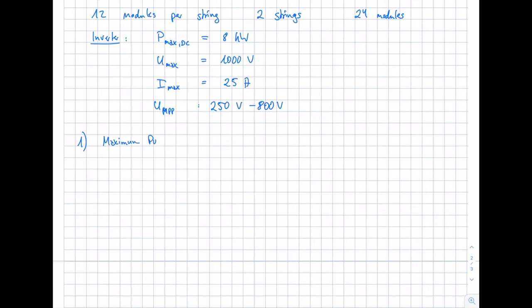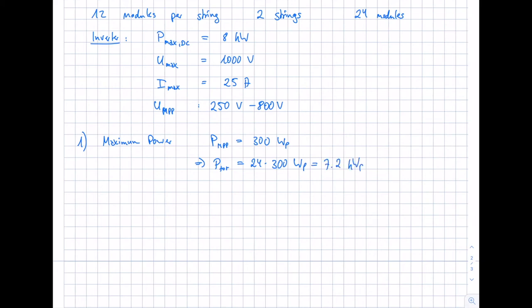Criterion one — maximum power: our module has an MPP power of 300 watts, and we have 24 modules total (12 per string, two strings). That gives us a total power of 24 times 300 watt peak, which equals 7.2 kilowatt peak. This is smaller than the inverter's P-max of 8 kilowatts, so criterion one is fulfilled.